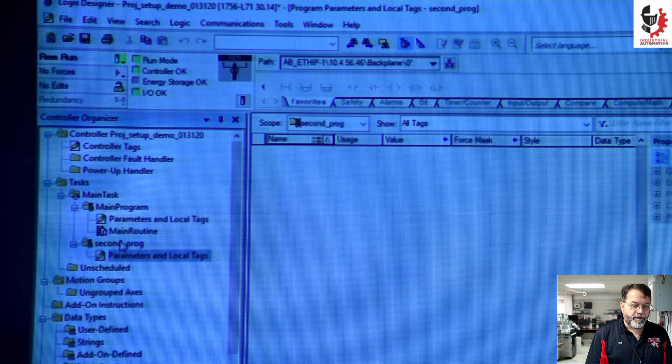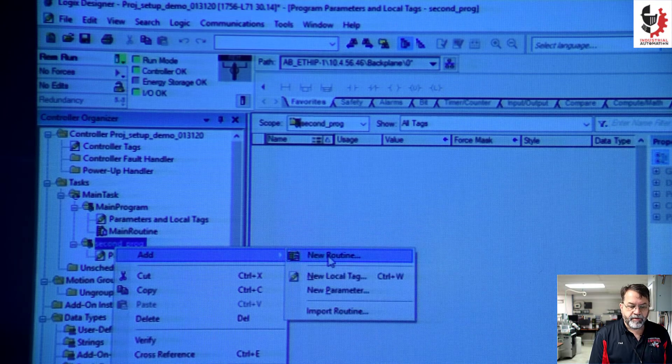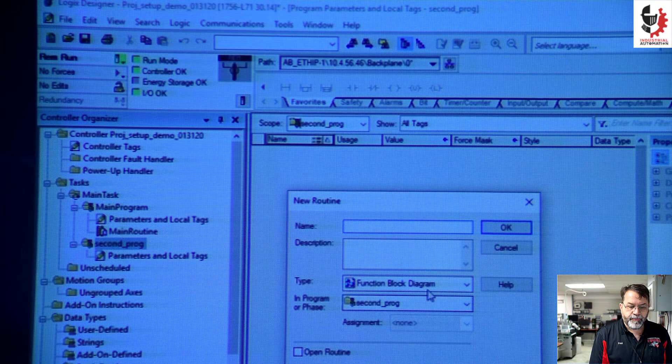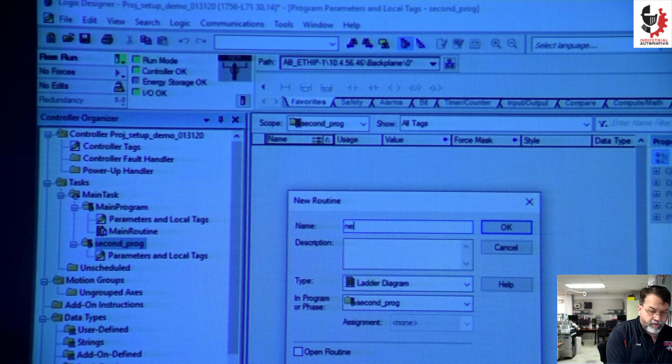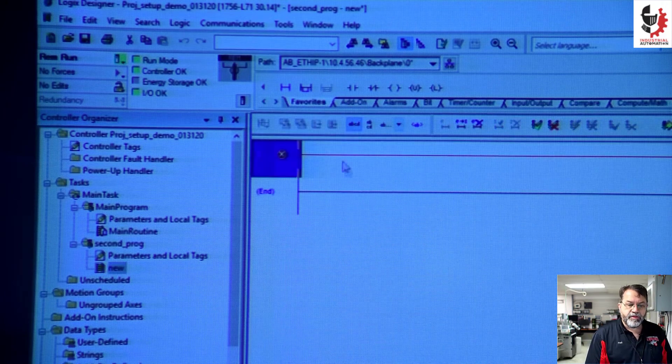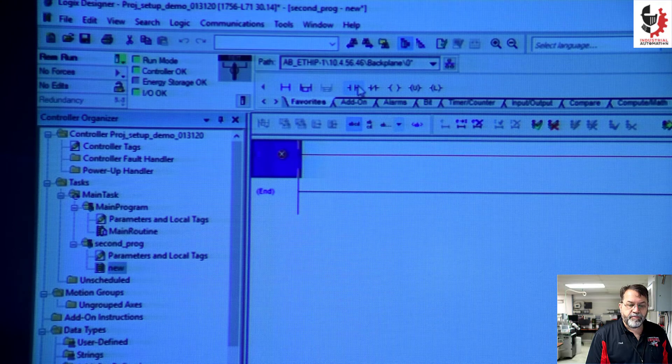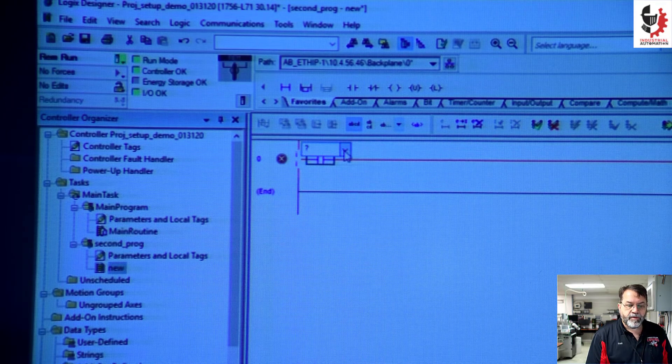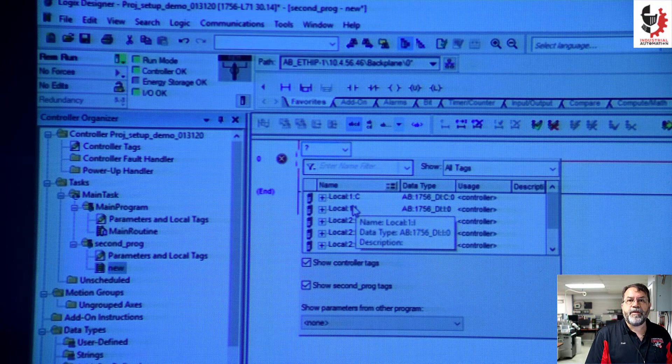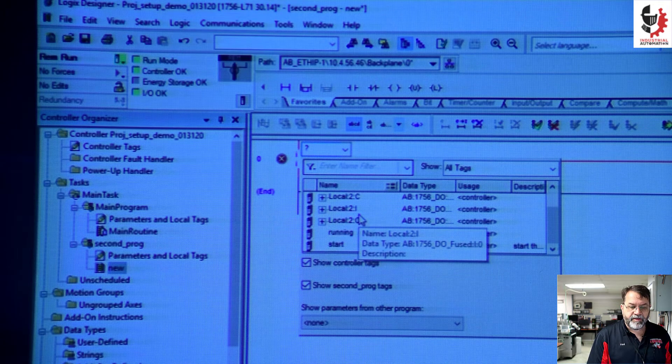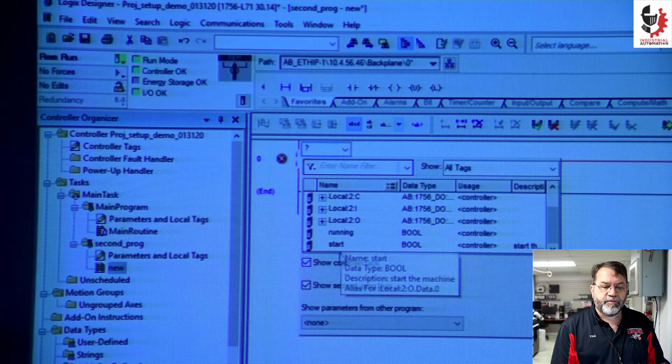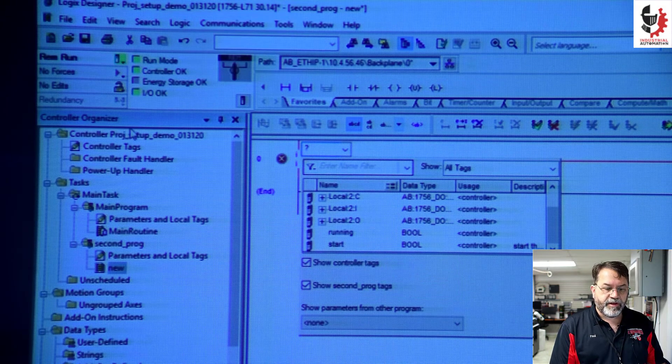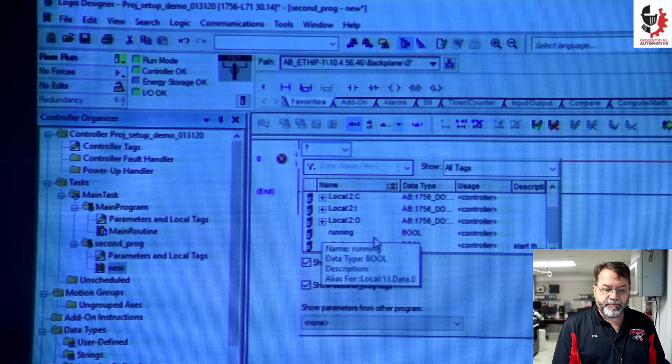Now, I'm going to create a routine in this new program. So right click, add new routine and I'm going to make that ladder logic. I'll just call it new. When I go in there, if I want to add an input and I go to assign that input, I've got my local addresses on my base tags. And notice I have running and start are both available to me because they're up in the controller tags. But that fault tag I made, it's not available here.